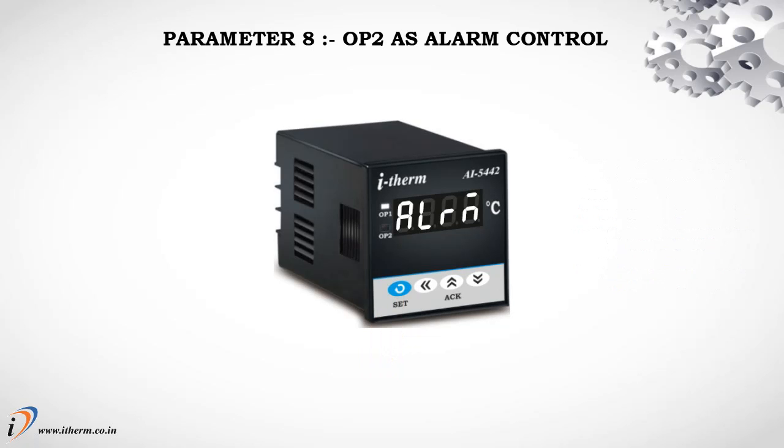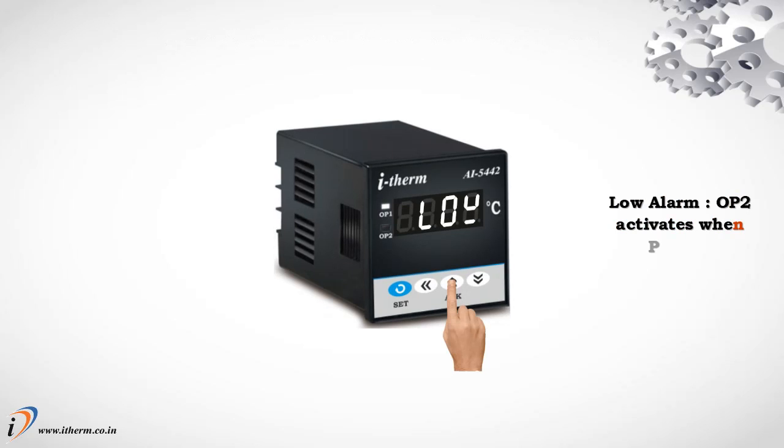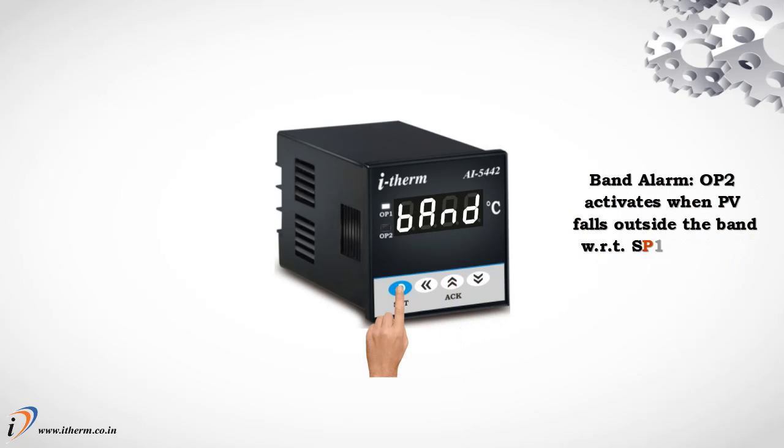Parameter 8. Output 2 as alarm control. Parameter 11. Output 2 as alarm type. Low alarm. Output 2 activates when process value is less than set point 2. High alarm. Output 2 activates when process value is greater than set point 2. Low deviation alarm. Output 2 activates when process value is less than set point 1 plus minus set deviation value. Band alarm. Output 2 activates when process value falls outside the band with respect to set point 1 in either direction.